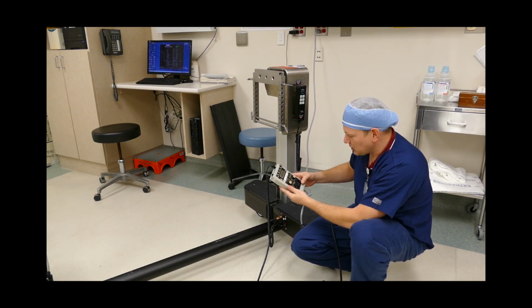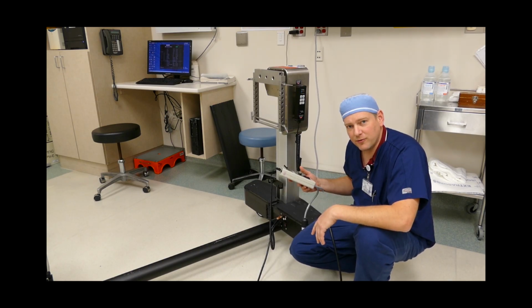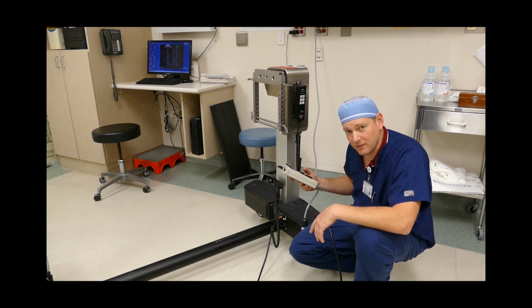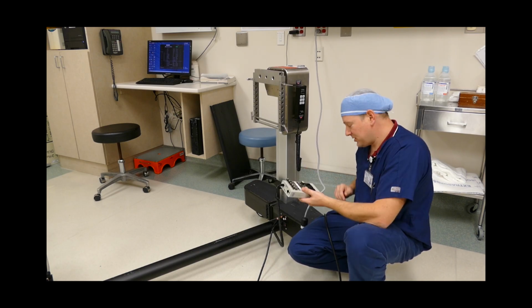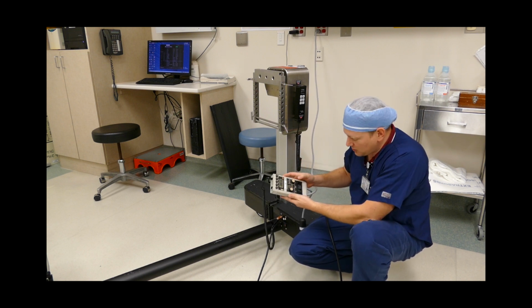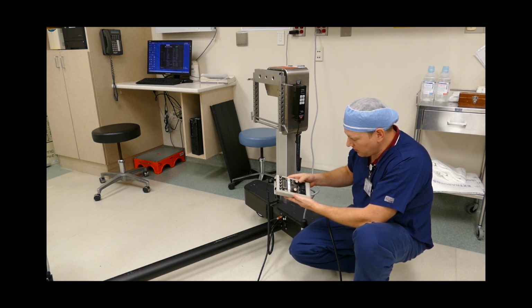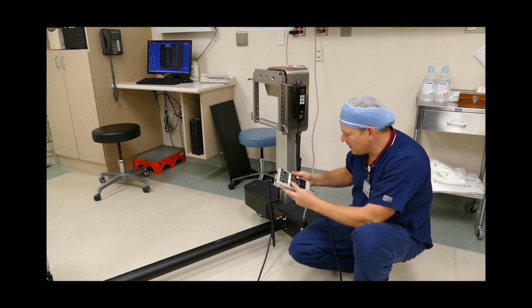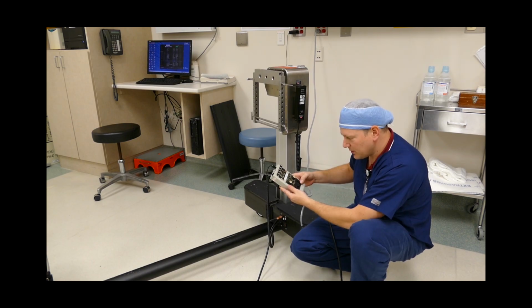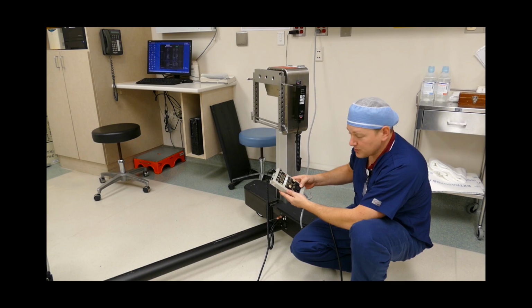Go down to enclosure leakage. This test is performed both with the power on and the power off. So first off, we're going to test it with the power off. Make sure that the power is off on the table. Make sure that the outlet is in normal and L2 is closed. Metering between 0 and 0. I lift ground. I've got 001.